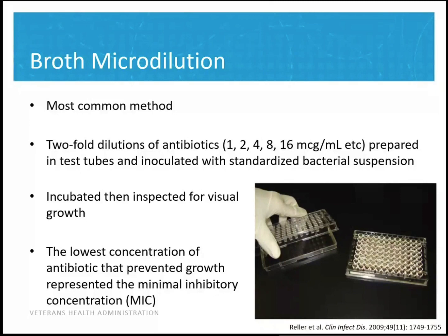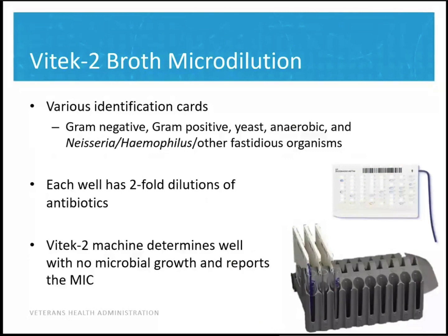As you can predict, broth microdilution is very time- and labor-intensive. Over at the VA, we use the VITEK-2 machine, which automates the whole process. Instead of separate test tubes, there are different wells on identification cards — gram-negative cards, gram-positive cards, etc. — each with a different two-fold dilution of antibiotics. The VITEK-2 machine reads the growth for you and reports out the MIC, saving time and money.